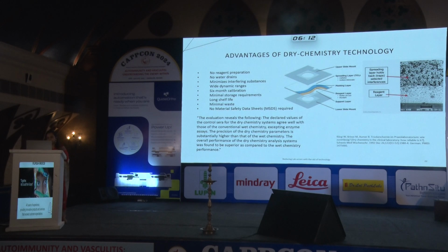So these are the advantages of having a dry chemistry analyzer in our lab. No reagent preparation required, no water drains, minimizes interfering substances, wide dynamic ranges, 6 monthly calibration, minimal storage requirements, long shelf life, minimal waste, and no MSDS required.